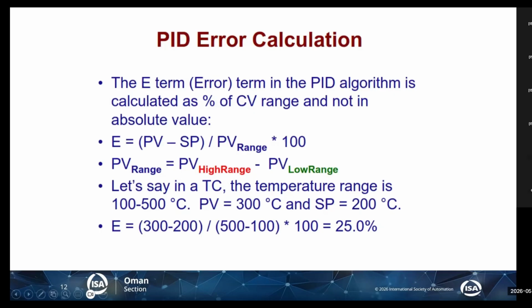Then here we have something called error. As we mentioned, a PID controller is nothing other than a control algorithm that automatically adjusts the process. This adjustment is based on error. If there is an error between the process value and the set point, then the PID effect will come, and we will see this in the algorithm. How do we calculate the error? Basically, people say it's PV minus SP, but how DCS and PLC systems understand it is in percentage and in PV range, and this is very important. So error is equal to (PV minus SP) divided by PV range, times 100.